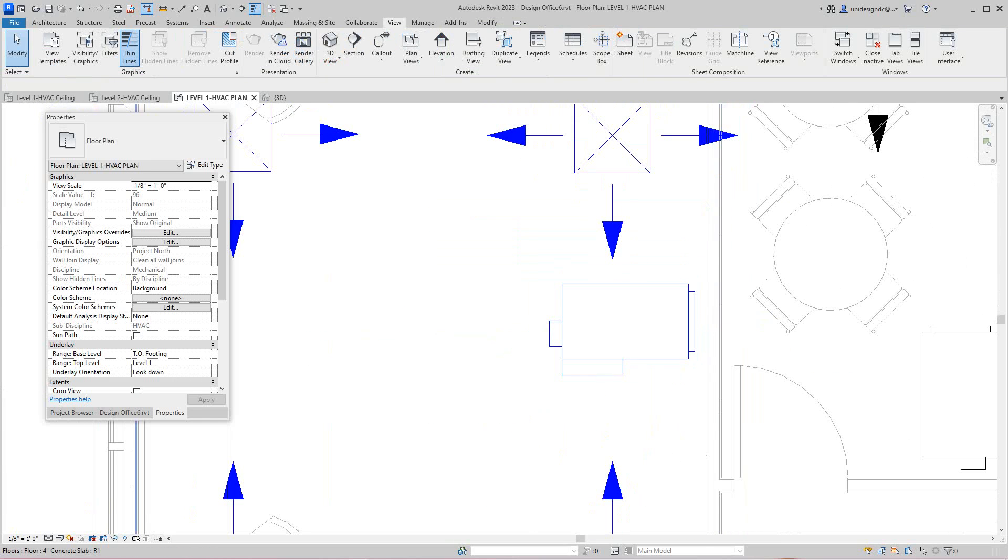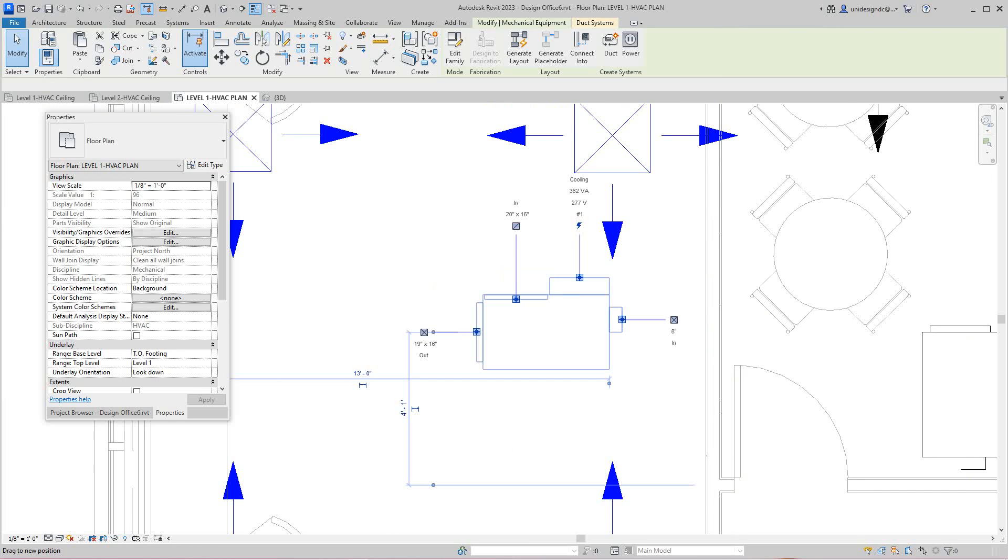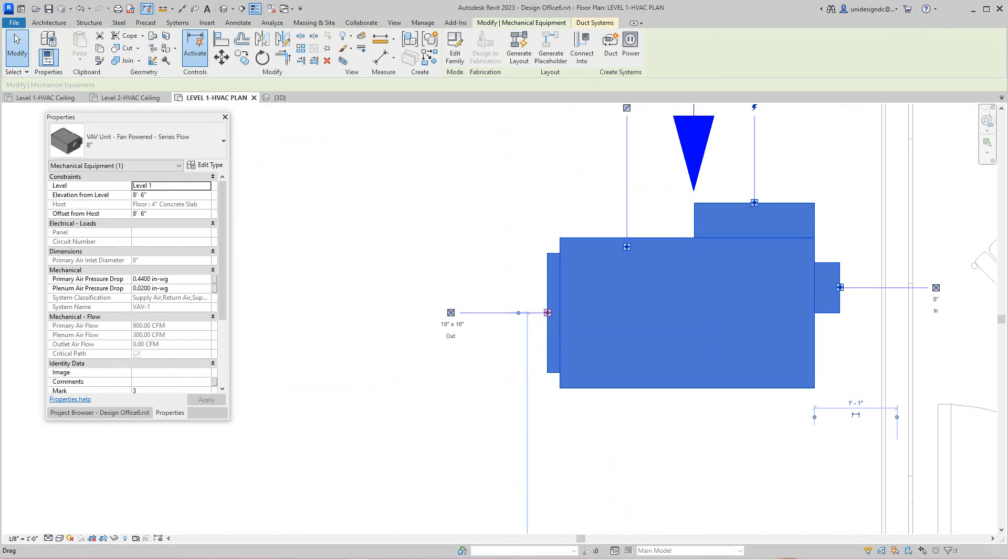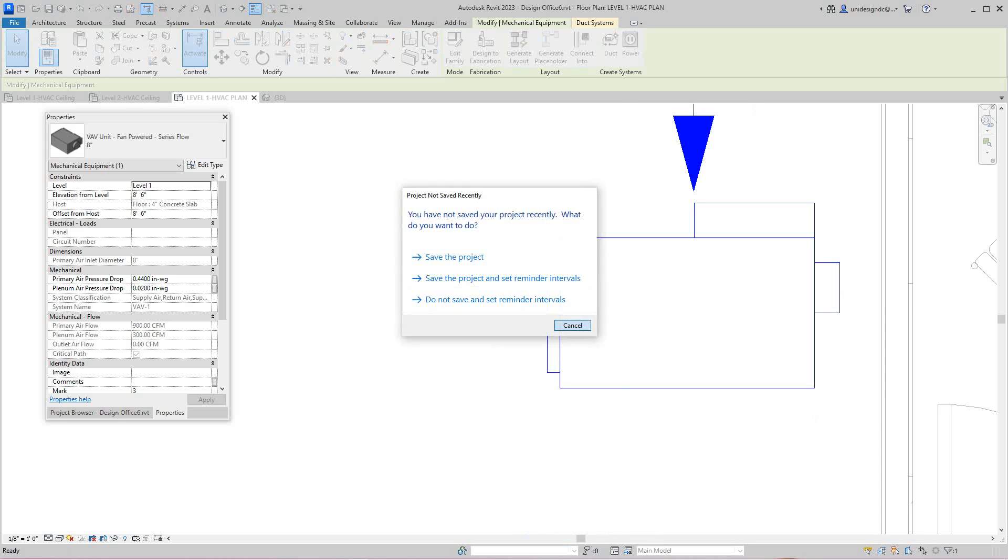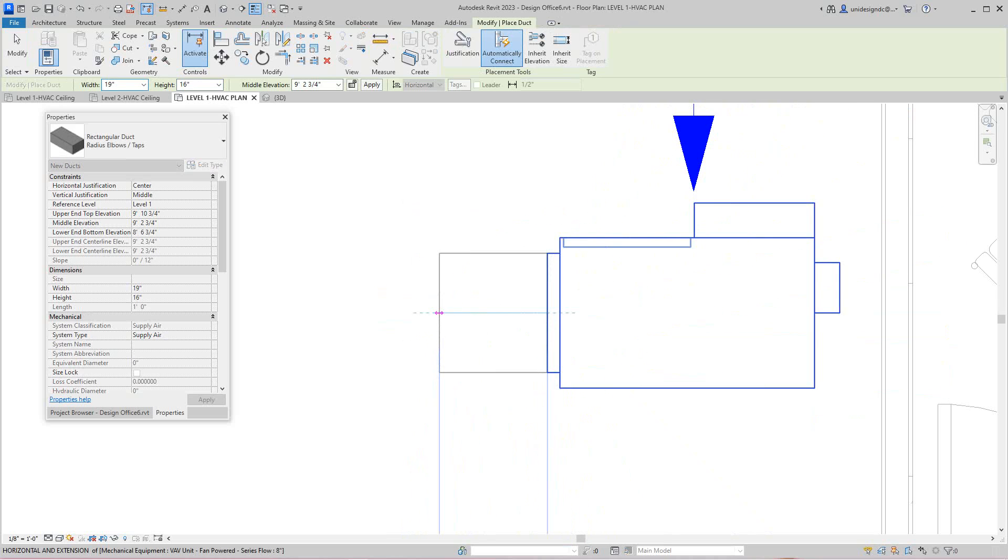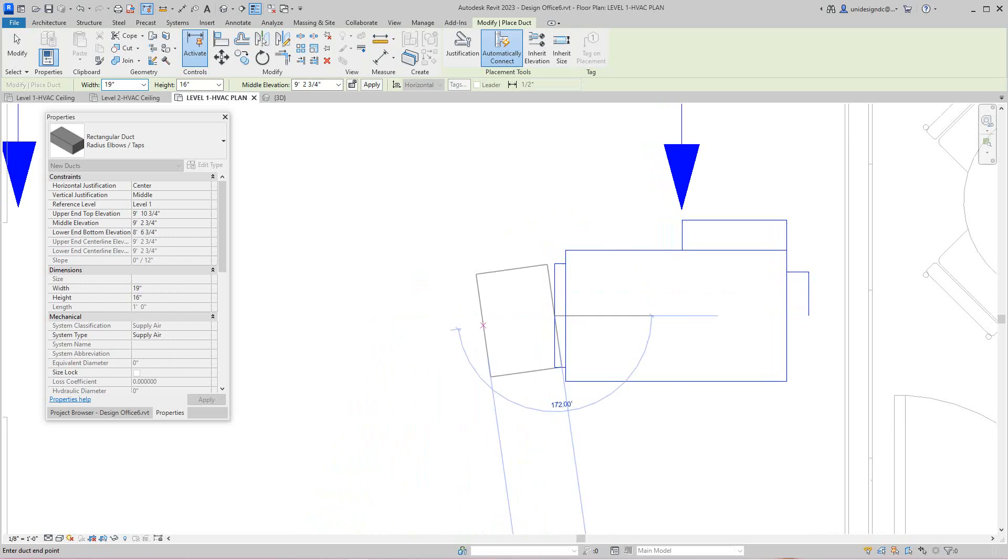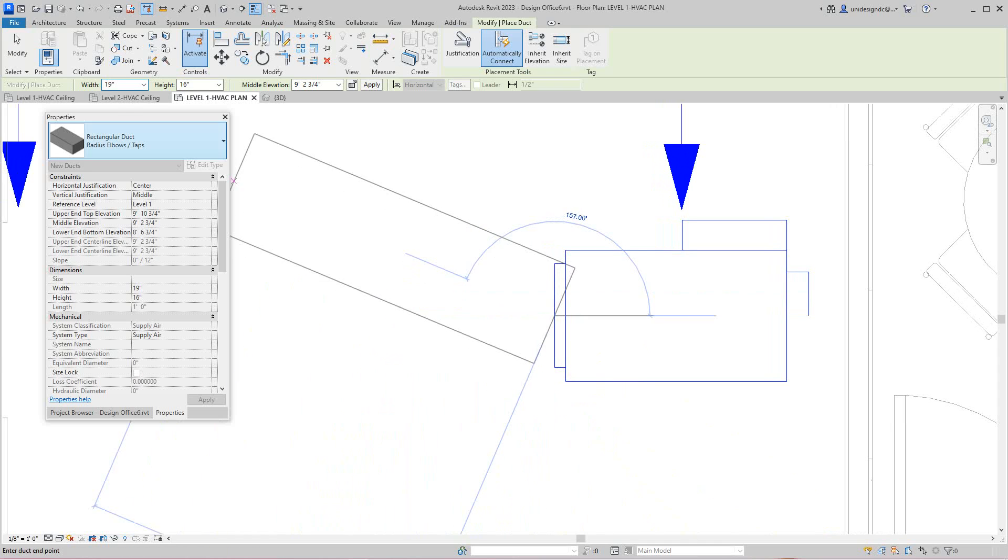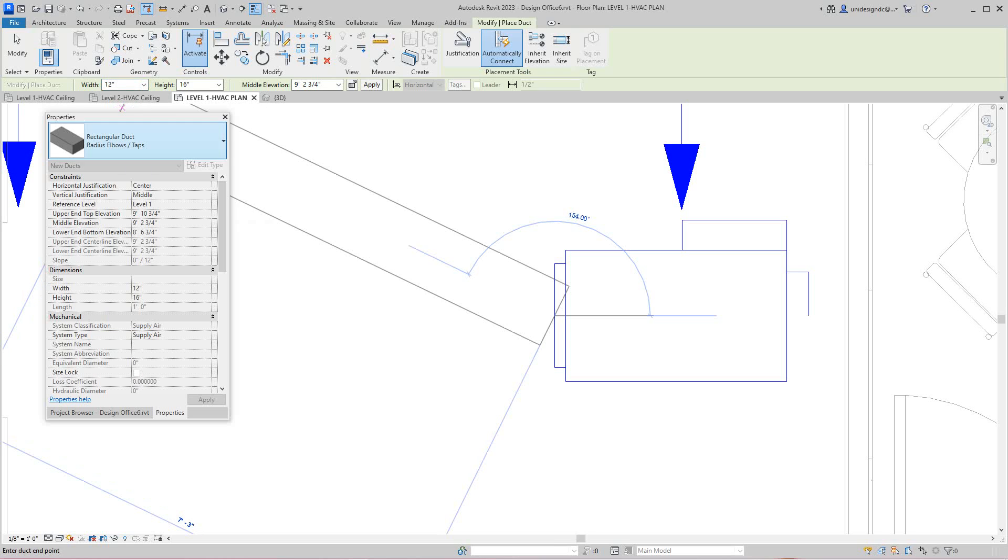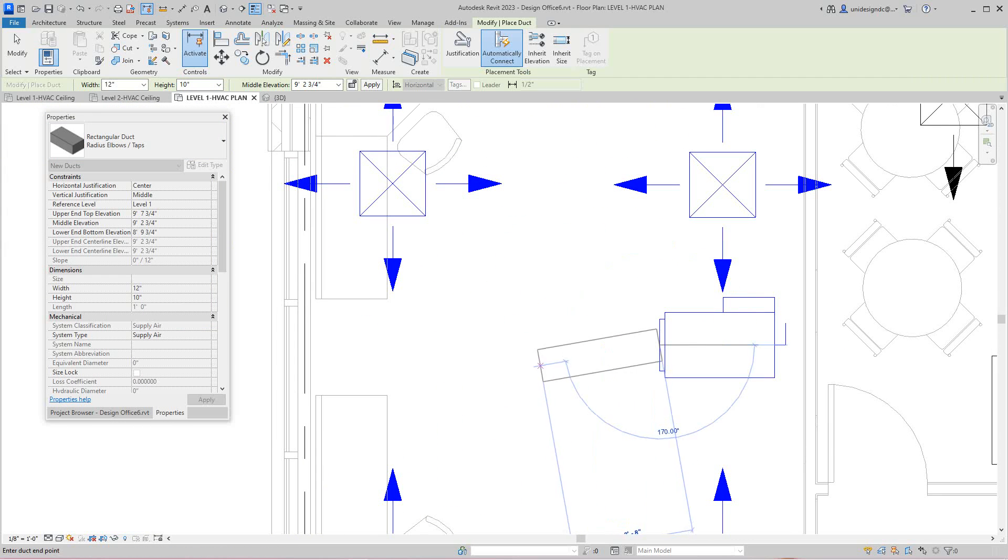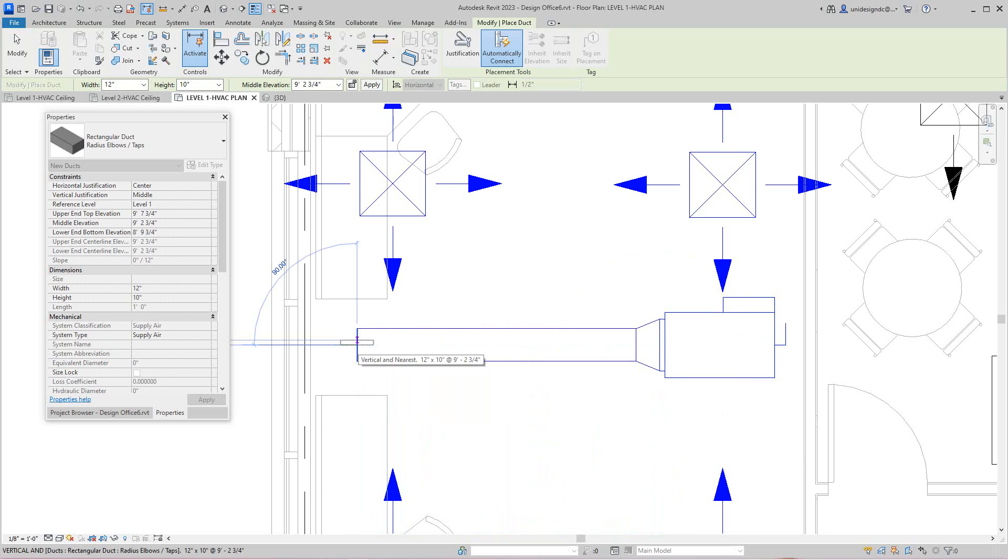This is kind of tricky. So basically what we want to do here, we want to zoom into our VAV unit. We want this duct right here, so we can rotate this guy around. If I select this connector and right-click and say draw duct, it's going to give me the duct size that was on that connector. This is 19 by 16, which I don't really want. I want to take it down here, so let's drop this down to 12 and it's going to be 10. I'm going to bring it and just drop it right about there. So there's my main run for this system.